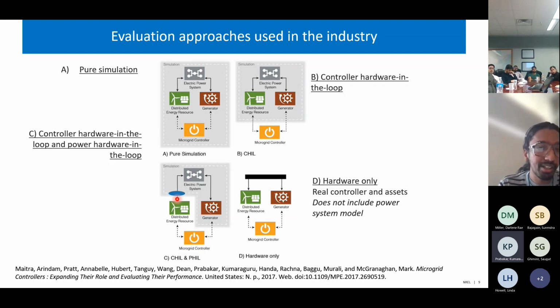For example, we can model the Washington State power system in DRTS and then assume you're going to add a large PV plant. You can bring those PV into the lab—let's say a 1.5 megawatt PV plant. We can bring it to our lab facility or any facility and run experiments with it. If you have microgrid controls, diesel gen controls, or cap bank controls, you can see how all of that interacts together.